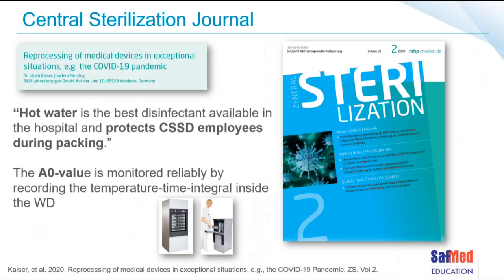A paper published in 2020 in the Central Sterilization Journal — printed in both English and German and specific to CSSD matters — was titled 'Reprocessing of Medical Devices in Exceptional Situations,' for example the COVID-19 pandemic. The statement in this publication is really valuable: hot water is the best disinfectant available in the hospital and protects the CSSD employees during packaging, and that the A0 value is monitored reliably by recording the temperature-time integral inside the washer disinfector. The washer disinfector helps protect both the patient and the staff.